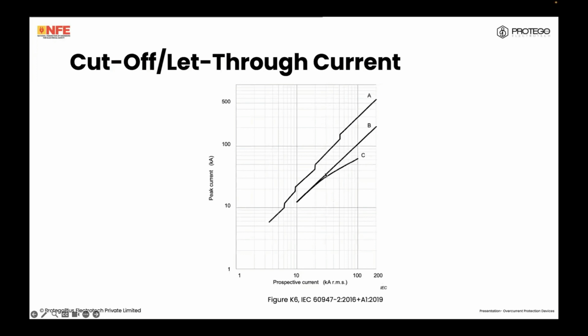say that this curve B is what I wanted to focus at first. If this is the prospective current, this will be the current let through without any protective device or without any current limiting. So, it will be just a 1-for-1 ratio. When the OCPD is introduced in the circuit, it is able to limit the magnitude of current, a fault current seen, and therefore the peak current seen. Therefore, there will be a lower value.